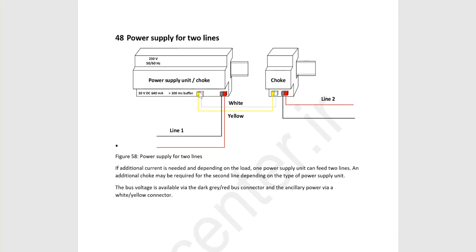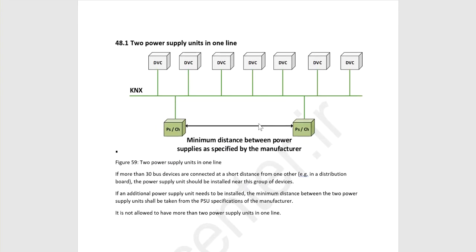So here I said the yellow and white, you can connect it to the choke and power up another line. It is possible. You can use 2 power supply in one line maximum, but it should have some minimum distances. Who said this minimum distances? You should pick it up from the manufacturer datasheet, okay? But in KNX, the documents sometimes say it should have 200 meter distance. For some power supply units, there is no any distance. For example, new Siemens type, there is no need to any distance. You can put it to each other.